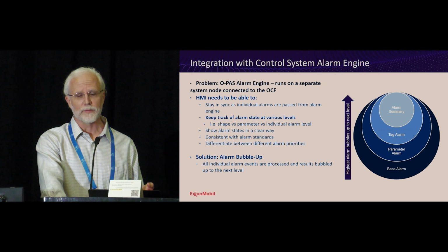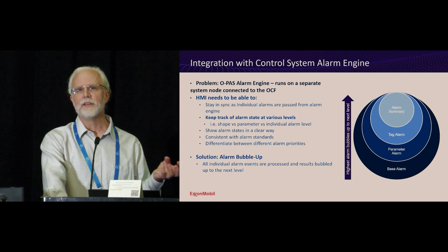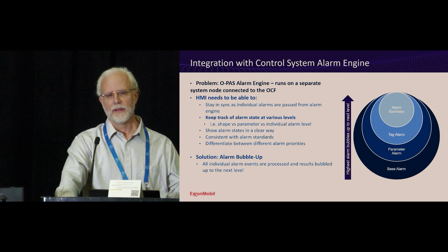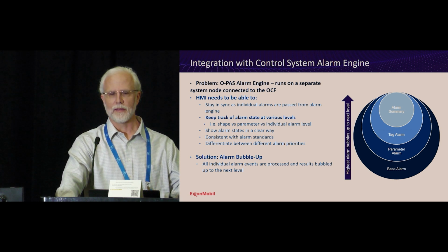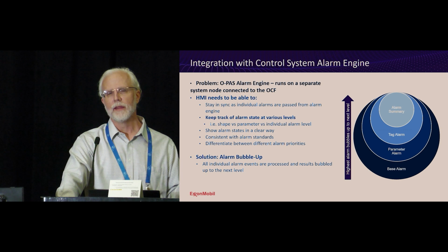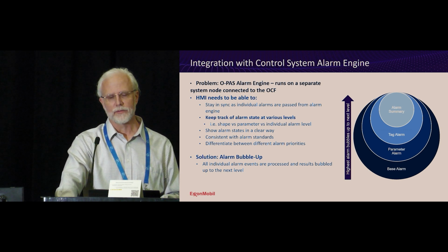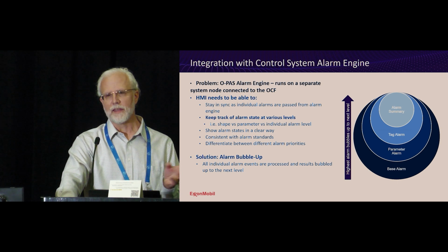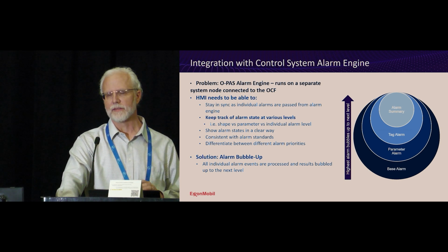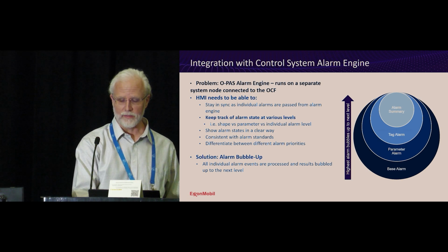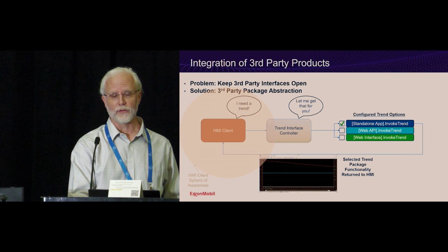So in the case of alarms, for example, the alarm engine lives on each individual controller. The master alarm summary is its own application by a separate third party. And of course, the HMI itself runs off of another server. So managing the integration of all these devices consistently within the HMI is a very strong challenge.